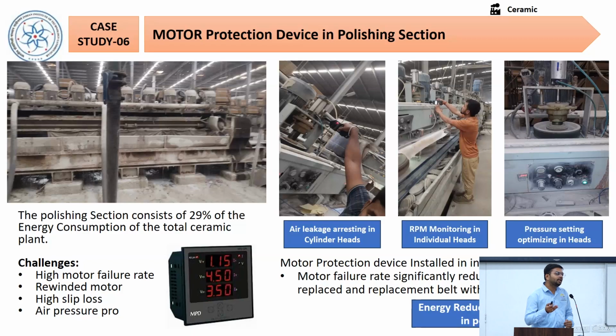Every head has a motor, and they have 14 heads in a row. So every motor has one or two rewindings. So we recommend that industries have a government energy efficient motor replacement policy, and adopt these ECMs. They process some ECMs, replace the motor, and have this energy motor protection device, and they get the savings now. So both problems are solved: the motor failure rate is eliminated, and the energy savings are also there.